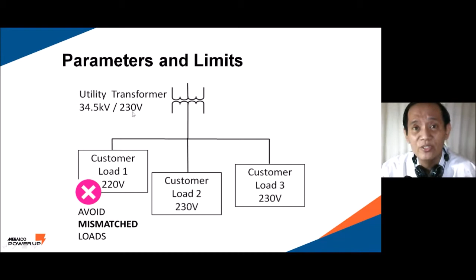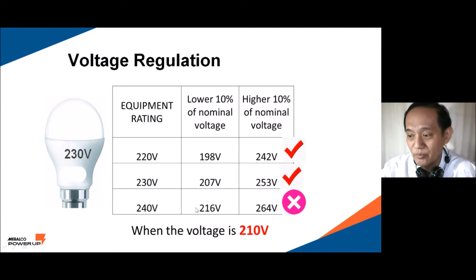So when the voltage that you measure is 245 and you have a nominal 230 volts, your 220 volt appliances, your 220 volt equipment will have problems because their upper limit is only 242 volts, while the actual measured voltage is 245 and well within the limits of the 230 volts plus or minus 10. The same way, when the voltage is lower at 210 volts, for 230 volts, no problem because it is still within that minus 10%. But when you have a 240 volt equipment, it could have problems. Its lower 10% is only 216 volts.